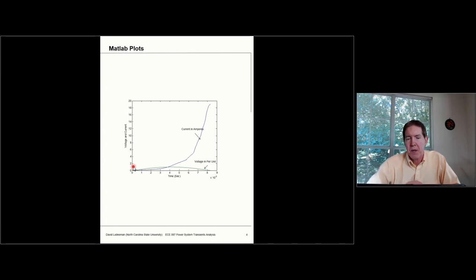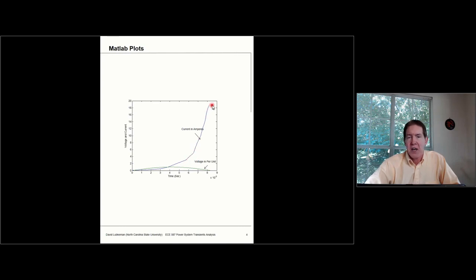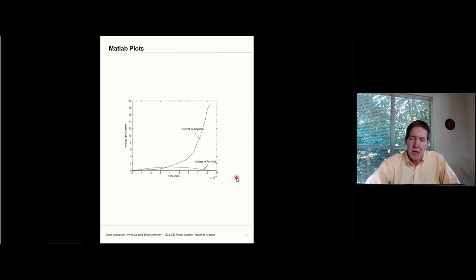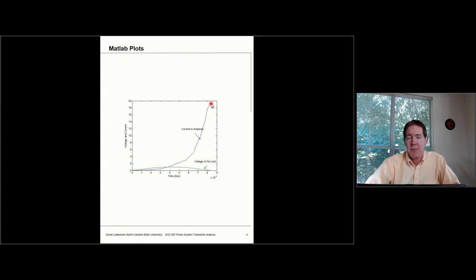What you end up with is a plot showing voltage at the bottom — going through one half cycle, energizing at a zero crossing. The current starts out really low, then jumps sharply as it enters the saturation region of the curve, eventually hitting the high peak value of 19 amps visible on the plot. After this, the current drops back off, and without any damping in this circuit, it oscillates between zero and the 19-amp peak. But what we're most interested in is this first cycle behavior.